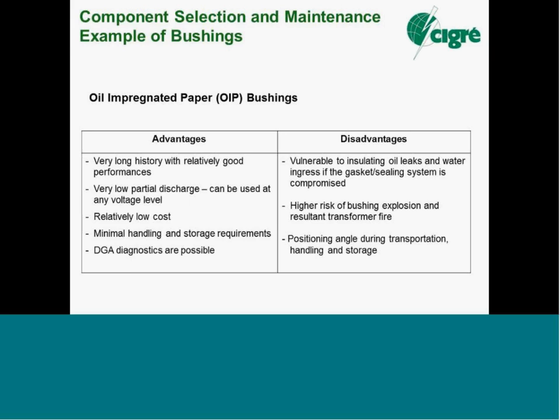It's well recognised that the OIP bushing, when it does fail, shatters the porcelain envelope, tends to drop the condenser core into the tank, drop into the transformer. So you've got an arc, an oil arc started. With failure of the bushing, you're now dropping this arcing oil fire into the transformer. You'll have oil under head pressure from the conservator going from the opening where the flange of the pin past this burning core. And so straight away you've got an oil fire triggered. So when it does fail, it has high risk of a resultant transformer fire. Total loss of the transformer possible.